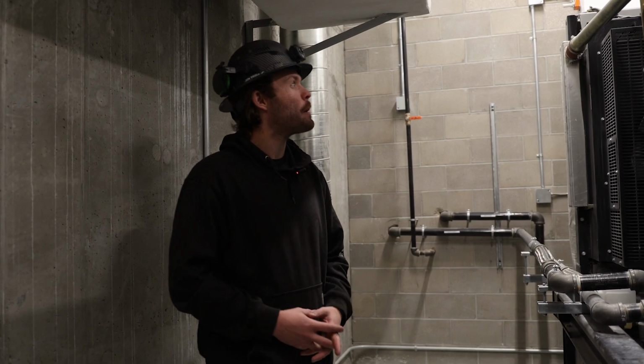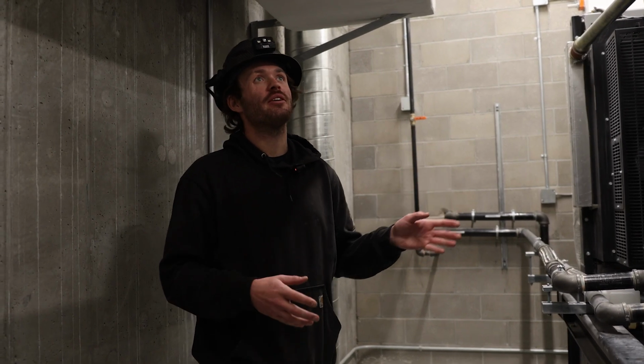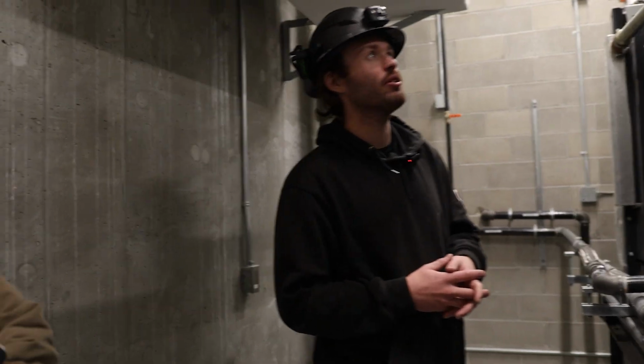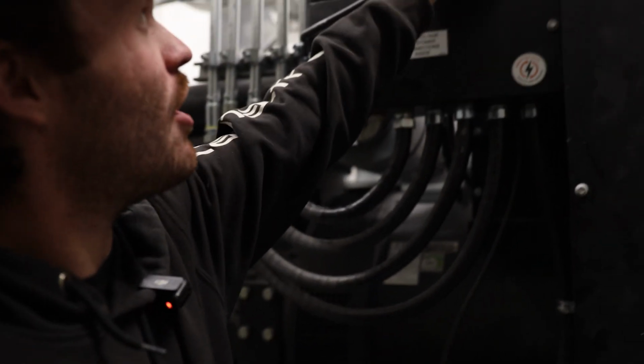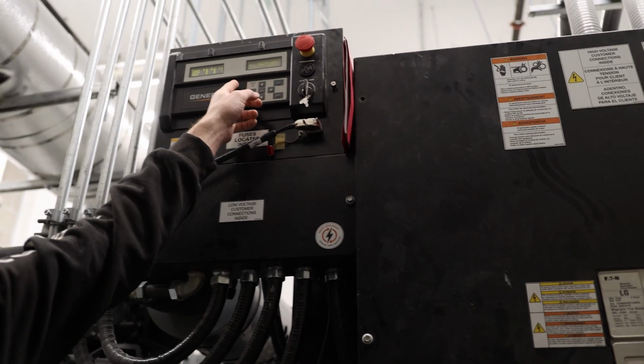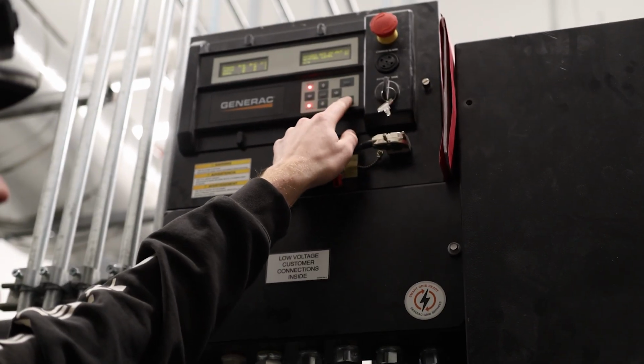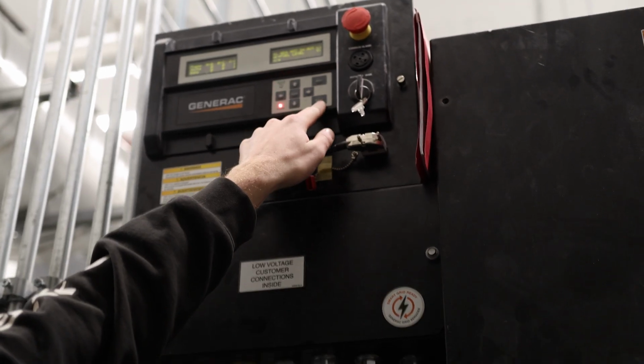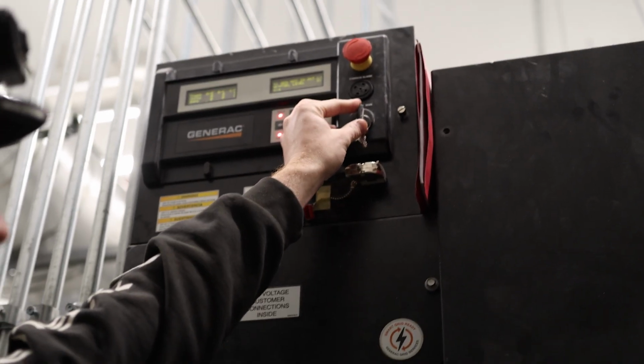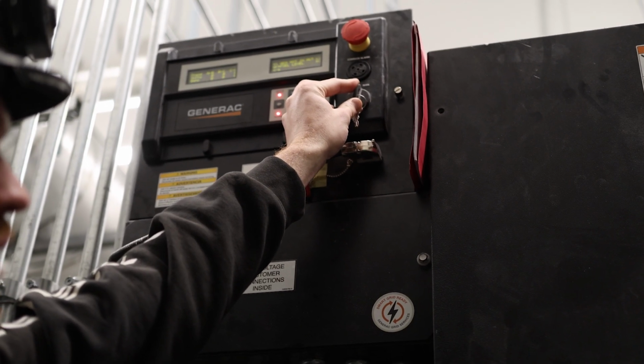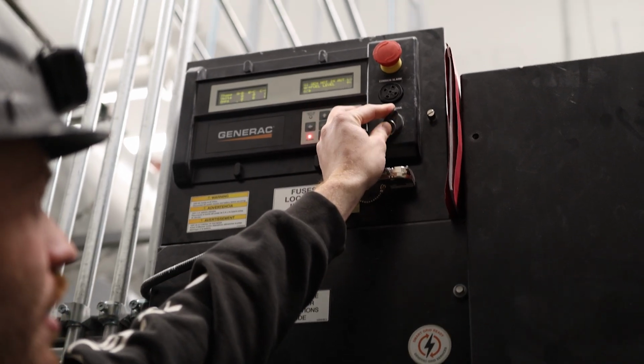Moving on, we'll show manually running this guy. We're going to get pretty noisy in here. So the key switch, generally it's going to be in our auto position. We'll flip it to off. It's going to beep at us. Hit enter, and that will silence it. And then you'll flip it to manual, and the unit will fire up and do its thing. Clean in here a bit too, because as you saw, papers flying, dust blowing.